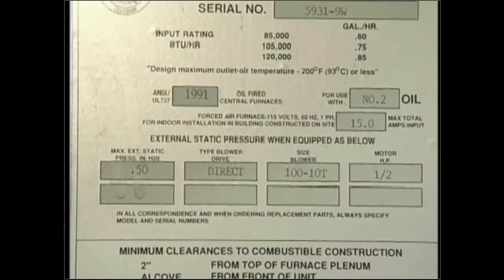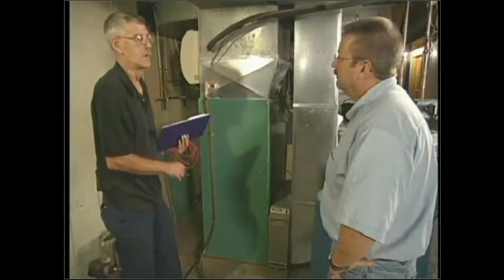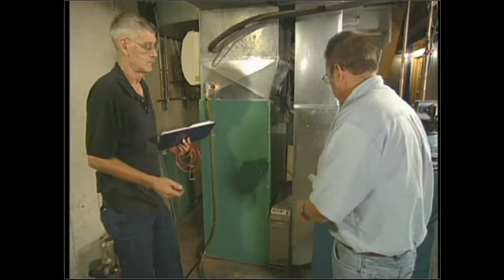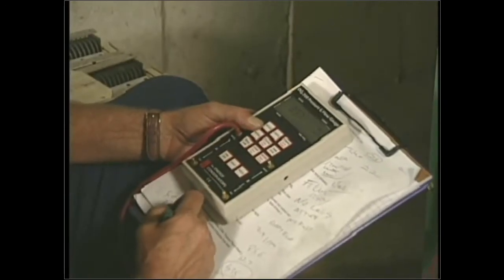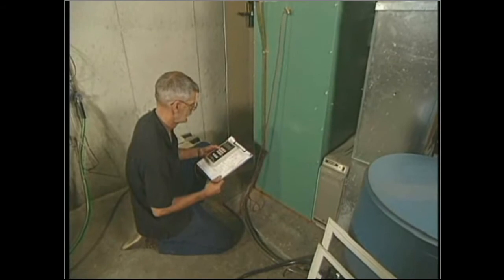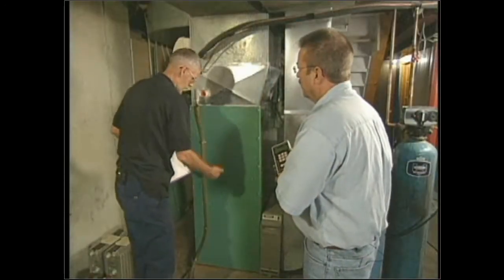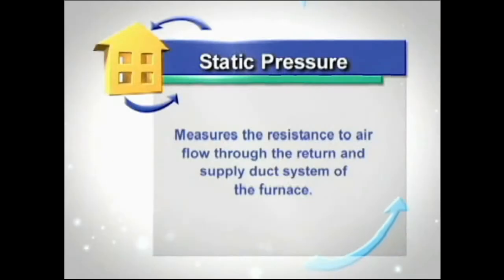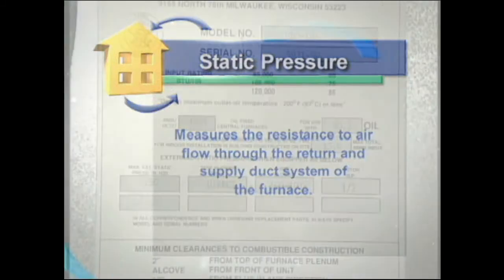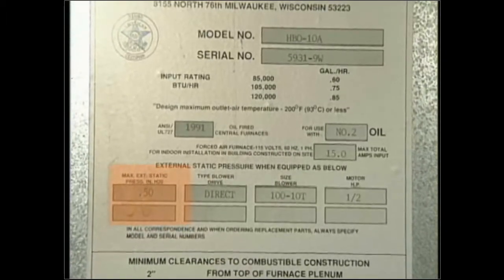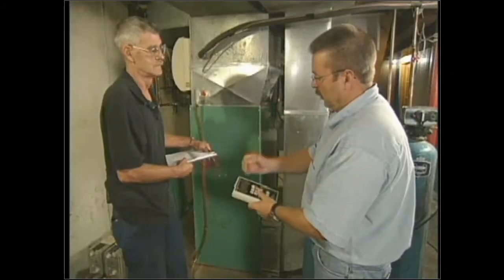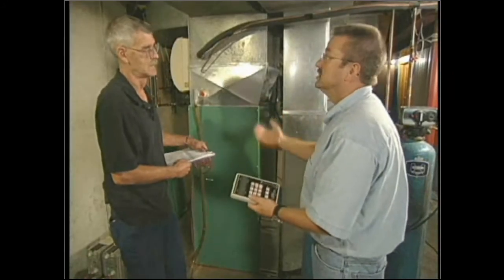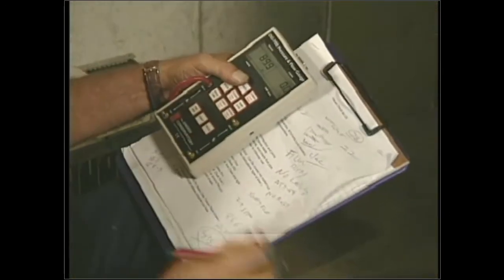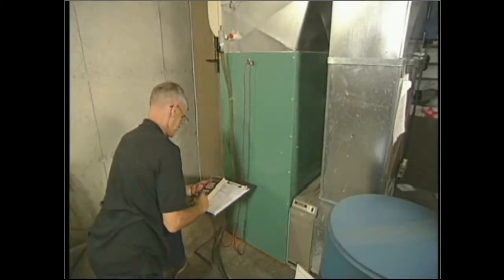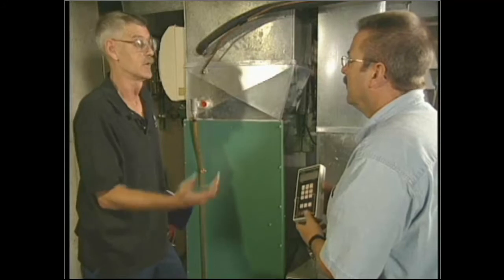And according to the PMI of this furnace, it cannot be greater than a ½ inch of water column, or 125 pascals. And again, you said you're using a manometer. Yep, the manometer is helping you with all the calculations, and it's helping you take the readings. Yes. So again, we use the manometer, point, get our probe down into the airflow, add the two together. Cannot be greater than a ½ inch of water column, or 125 pascals. Some of the more modern furnaces require about 0.3 inches of water column, but 90% of them say 0.5 inches of water column. And again, the auditor will document this, compare it to the PMI, and then make recommendations based on those. Yes. Higher statics in some areas mean that some decisions may need to be made on supply and returns. Like if the return is slightly higher, or the supply is slightly higher, you may need to add a supply, or you may need to correct the returns.